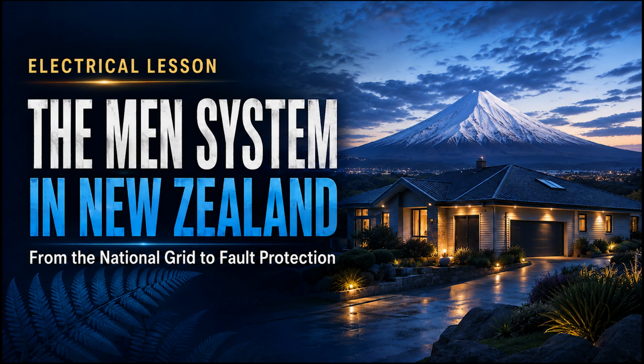Question 13. Why is a broken neutral dangerous? It can raise the installation earthing system above local earth potential and, on a 3-phase, 4-wire system, create damaging or dangerous voltage imbalance across single-phase loads. That completes our review, so let us finish by bringing the whole lesson back to one central idea. The New Zealand MEN system connects exposed conductive parts to the earthed supply neutral through a controlled low-impedance path, so that a fault causes rapid automatic disconnection of supply.